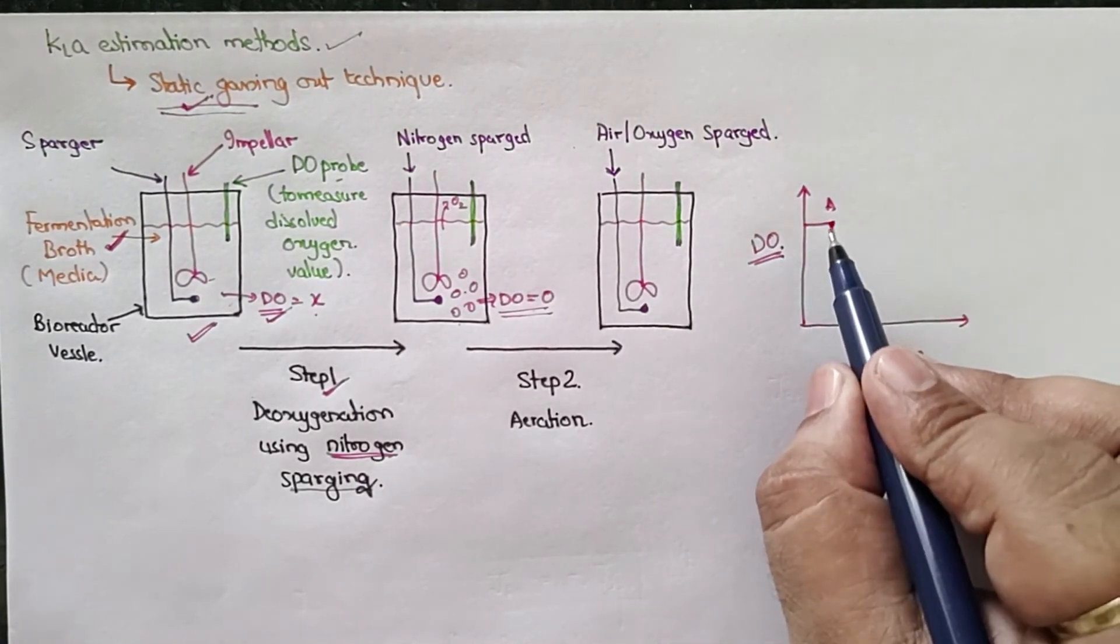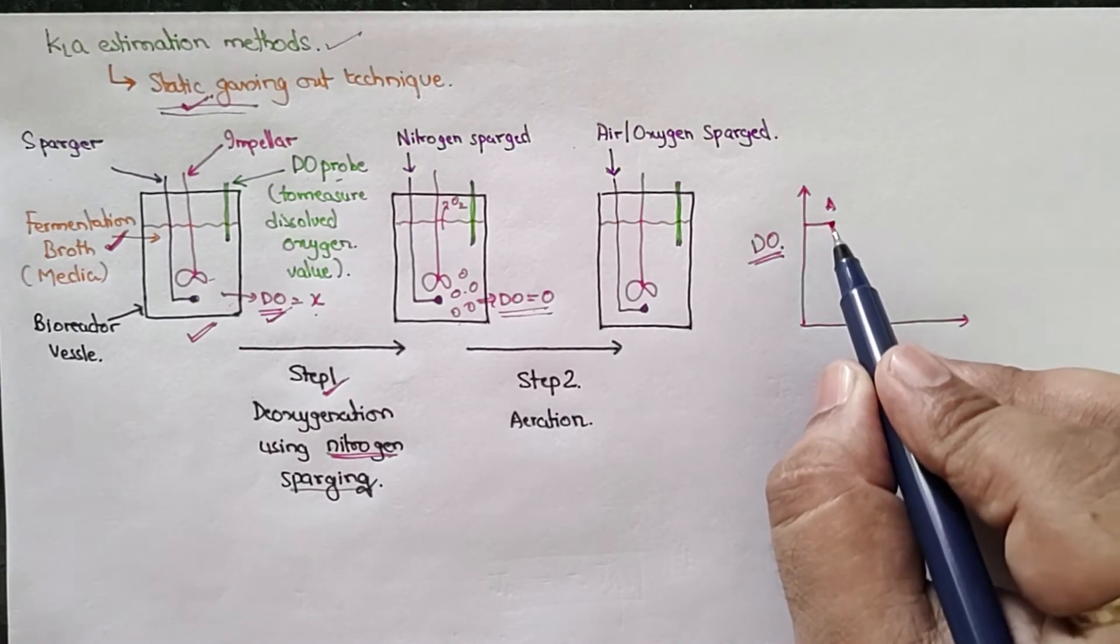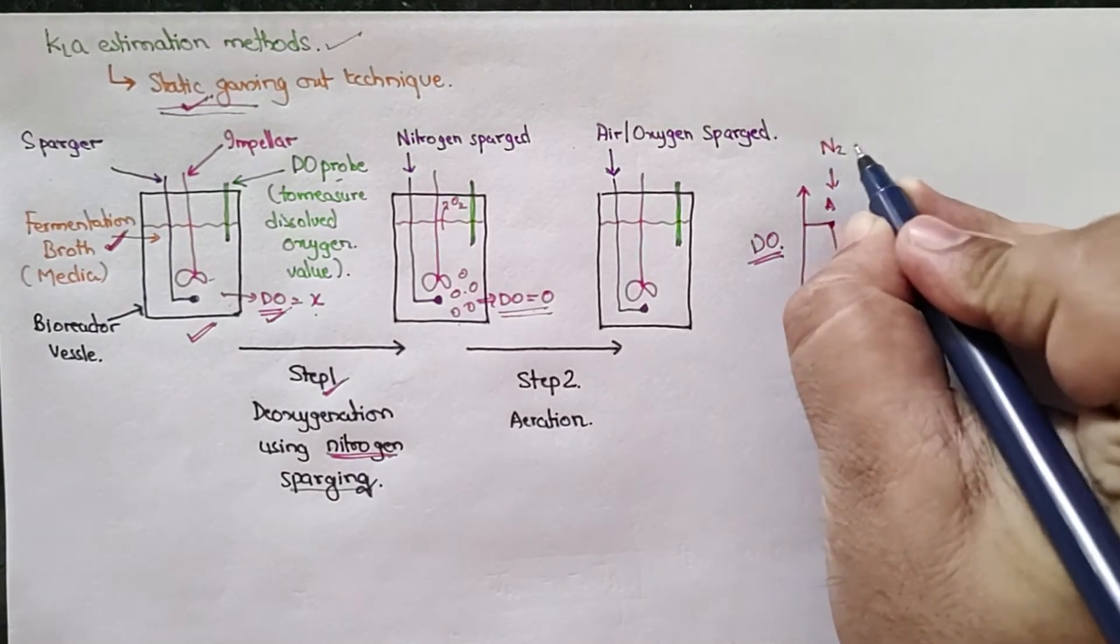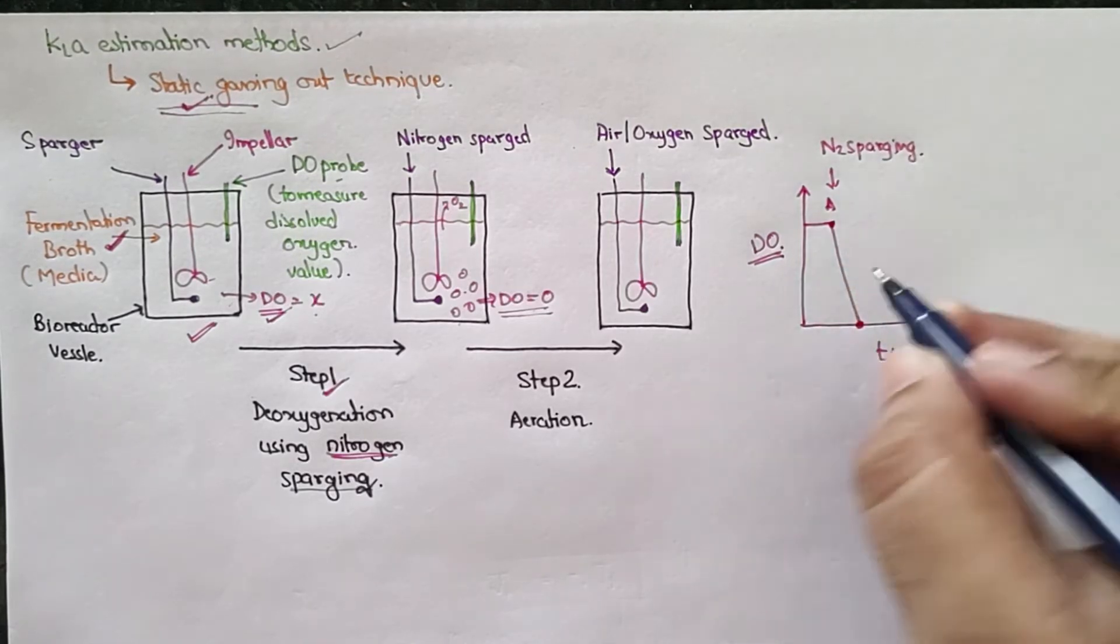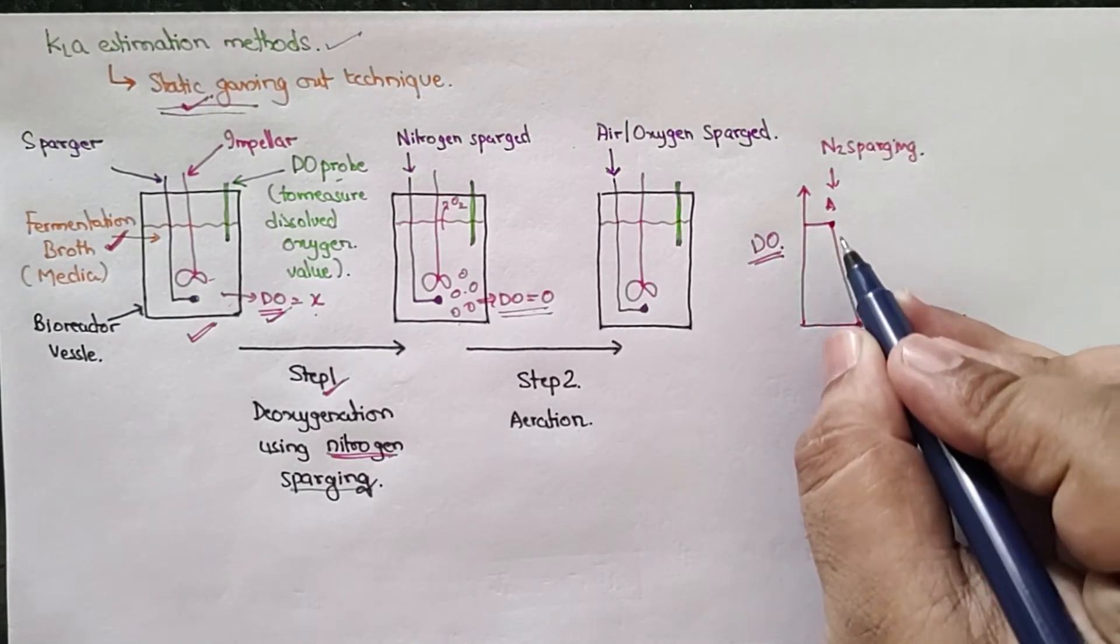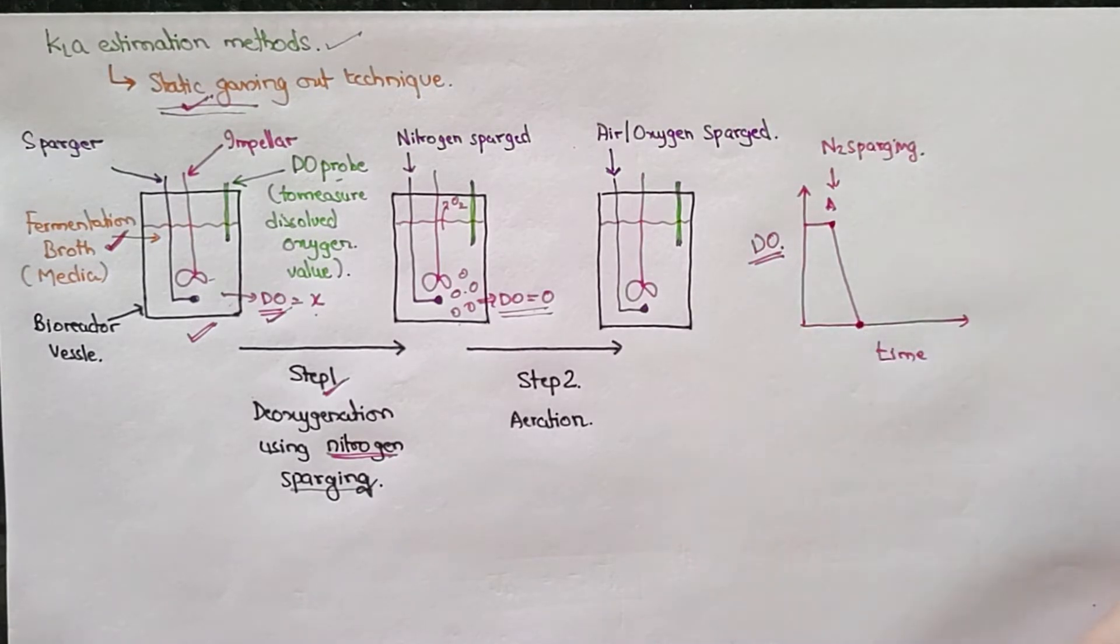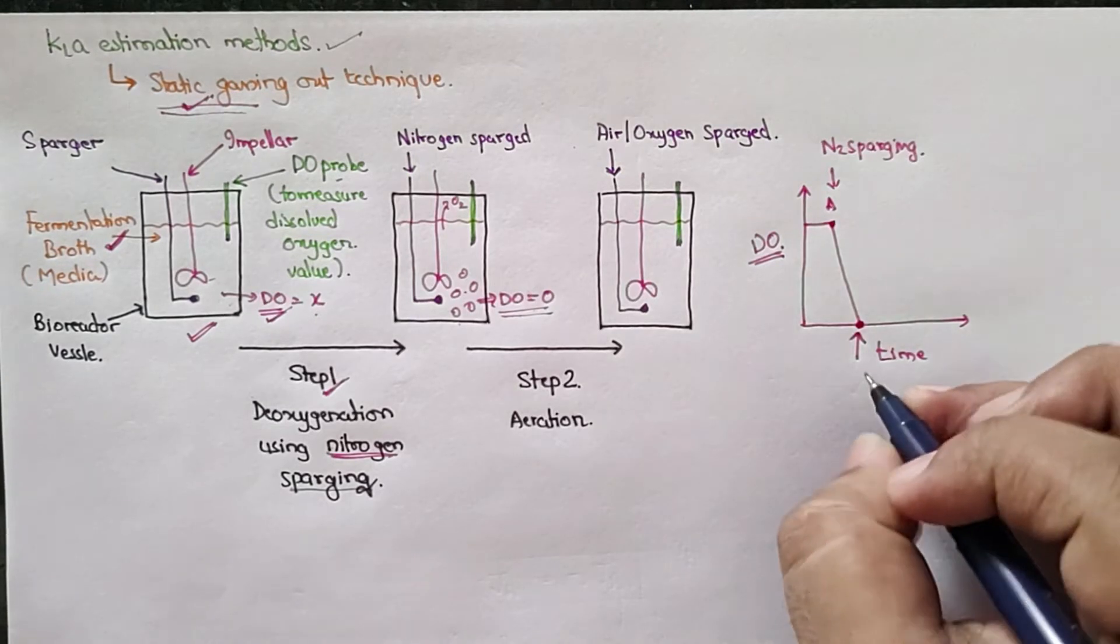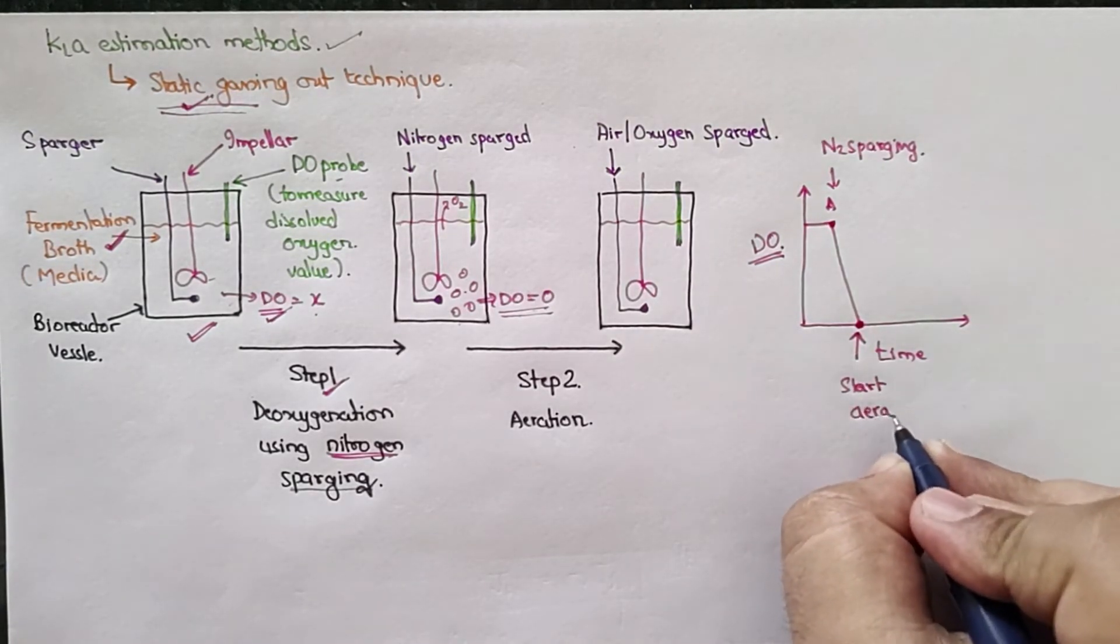So this is step A, when you start passing or sparging the nitrogen into the system. This nitrogen sparging will cause removal of oxygen or deoxygenation of the media, so the DO value will drop down to zero. At this point, you will start aeration again.